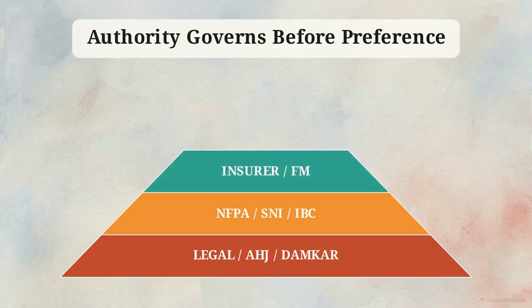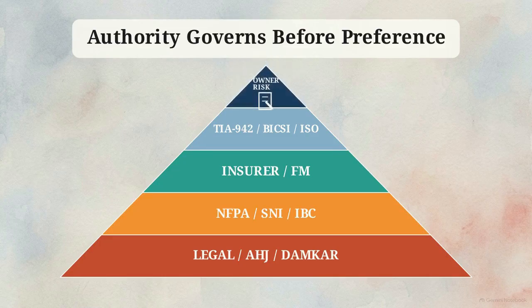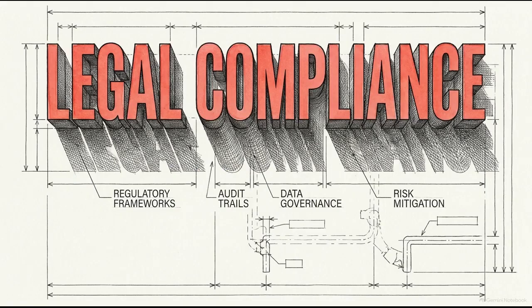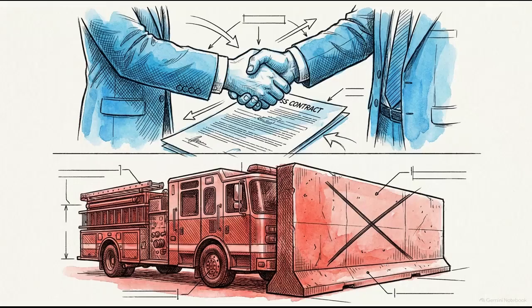basis. The middle layers shift from life safety to commercial protection. Insurers dictate property loss and business interruption requirements, while frameworks like TIA 942 define the IT infrastructure's operational reliability. At the peak of the pyramid sits the owner's risk policy. This is where operators define their residual downtime risk and final availability targets. The hierarchy enforces one strict rule: authority governs before preference. An owner can choose to accept a commercial risk up top, but they can never waive a statutory life safety or fire access requirement at the bottom.